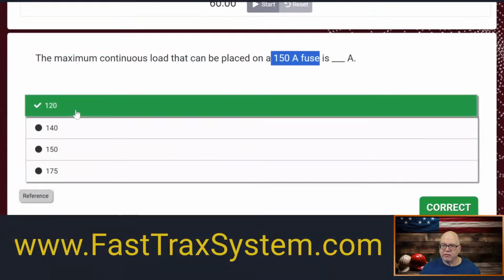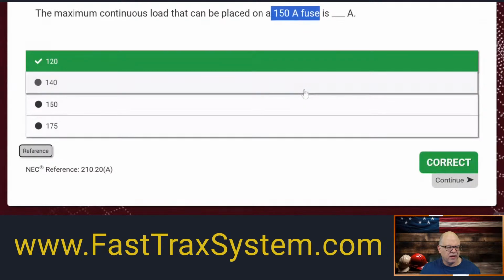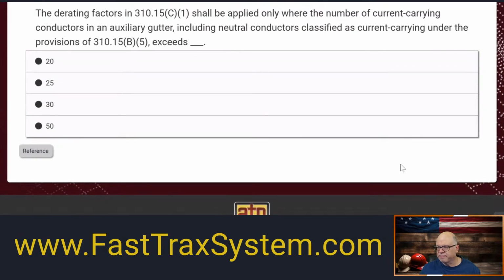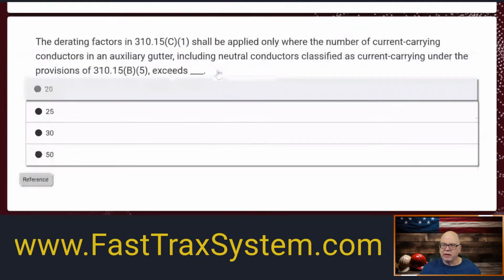If the question was different, and it said, what's the maximum rating of the fuse if it was 120 amps of continuous load, then it's 120 times 1.25, and you go size your breaker. If I'm given the breaker or fuse size, and I have to find out what the maximum I can put on it, then I go the other way. I take whatever the rating is of the device, and I multiply it by 80%. And see how they work? It's reciprocal. All right, so in this case, 120, and our code reference is right there, 210.20(A).